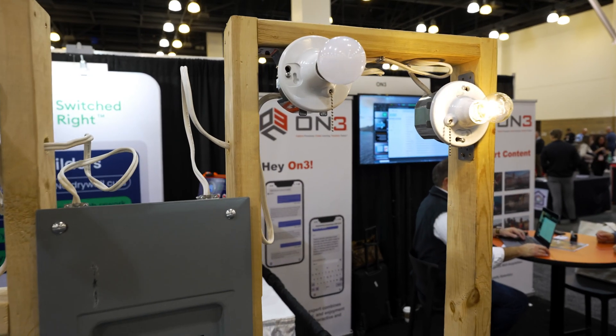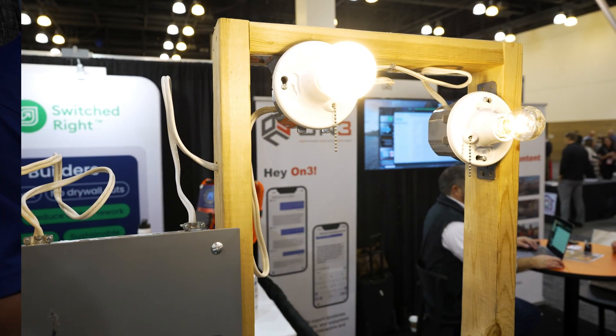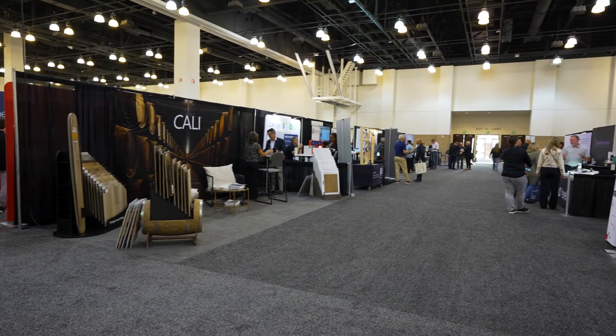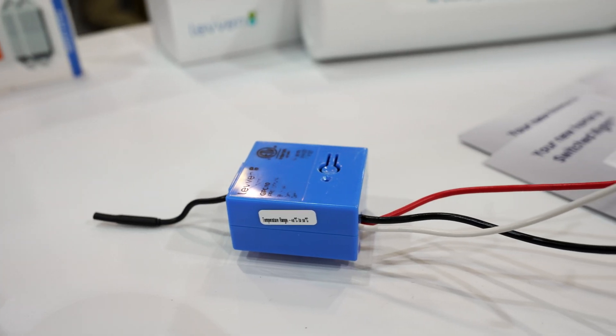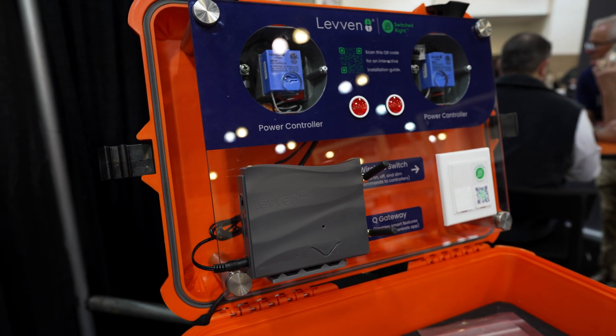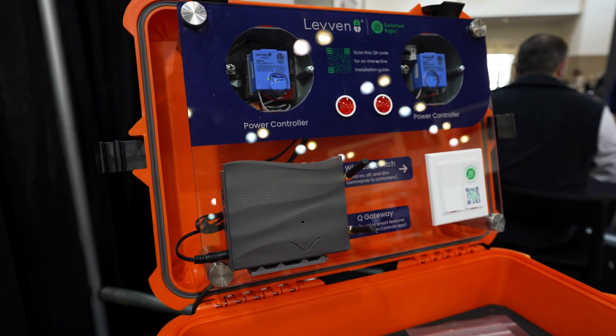By pressing and holding the switch, you can dim the light. Levven's wireless lighting controls use 900 megahertz broadband to communicate up to a distance of 300 feet unobstructed. In homes that have concrete and metal construction, we use that 900 megahertz to go through those building materials and allow for communication up to 250 feet. Each one of our power controllers acts as a mesh network, so that distance is from the closest controller to whichever switch is being activated.